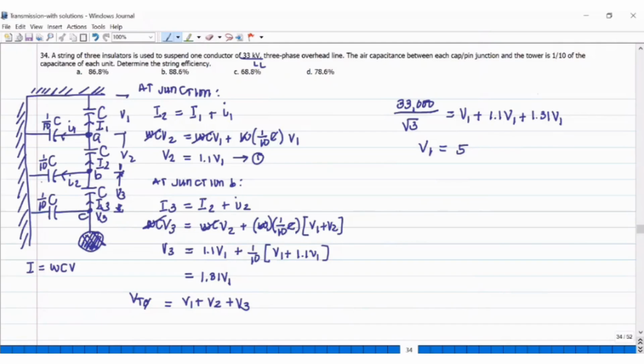5587.261. Yung V3, yun kasi yung pinakamalapit sa conductor. So 1.31 times V1, 5587.261. So 1.31 times yung answer natin na yung 7319.311 volts. Ang magiging string efficiency formula niya is equal to Vt per phase divided by N times the voltage at the nearest to the conductor times 100%.